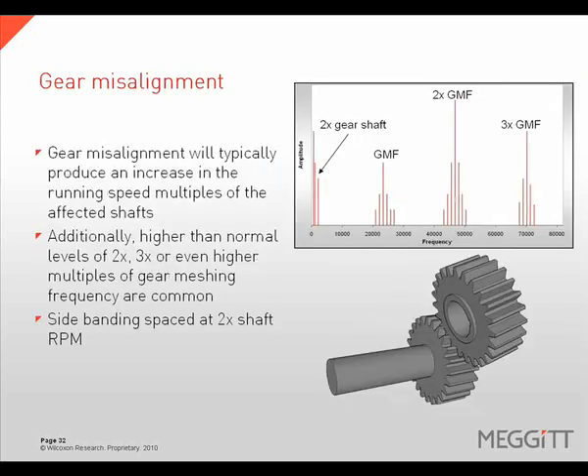Gear misalignment will produce an increase in running speed harmonics of the affected gears. Higher than normal levels of 2x, 3x, or even higher multiples of gear mesh frequency are common, with sidebanding spaced at 2 times the shaft's rotational speed.